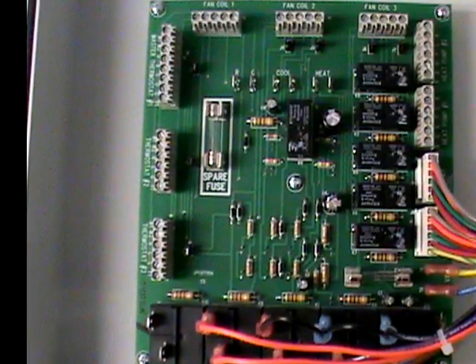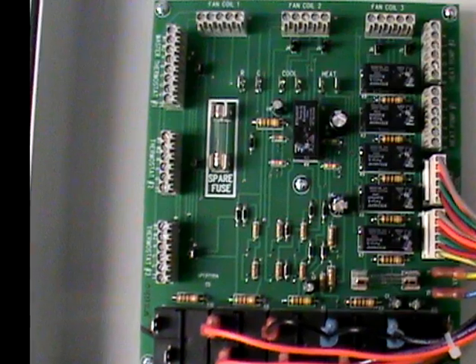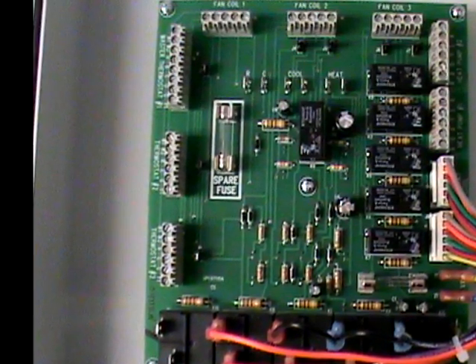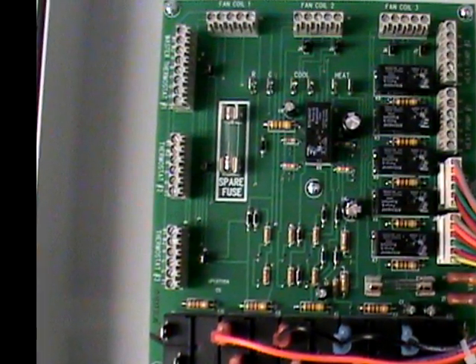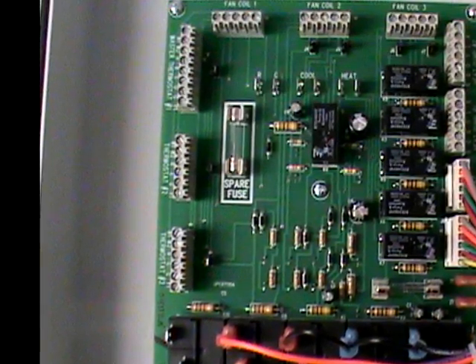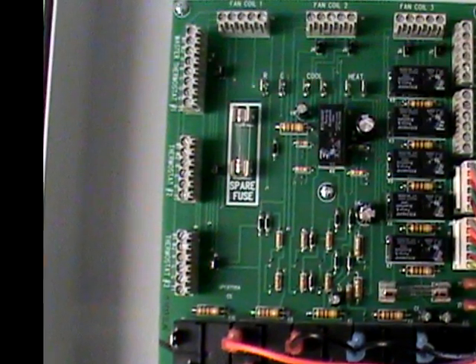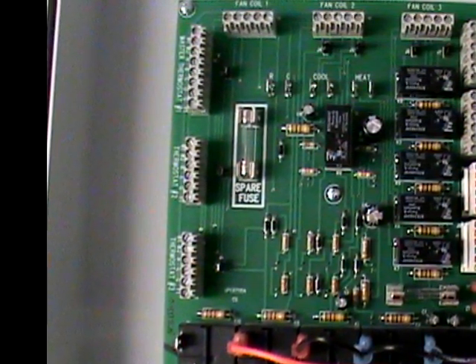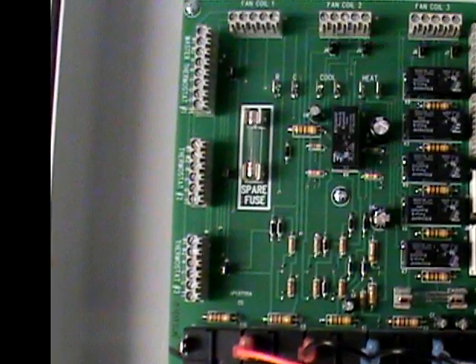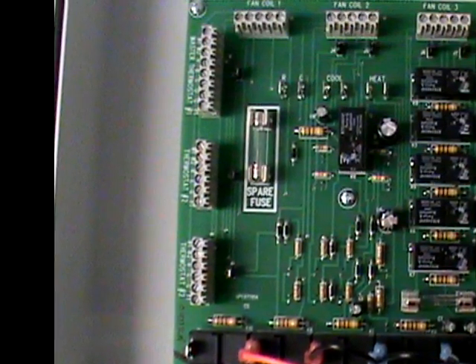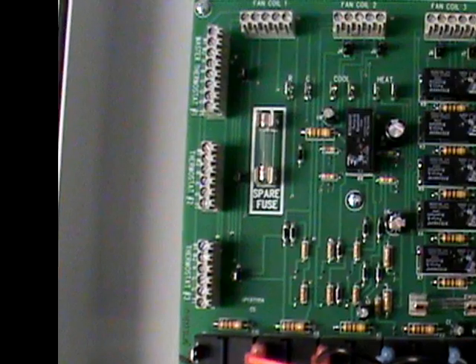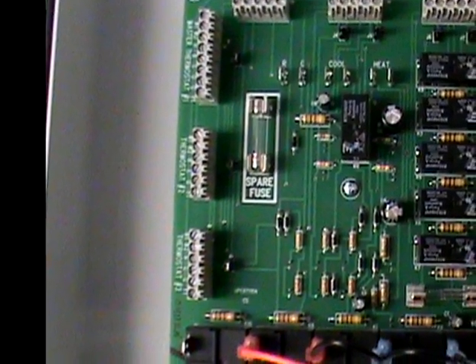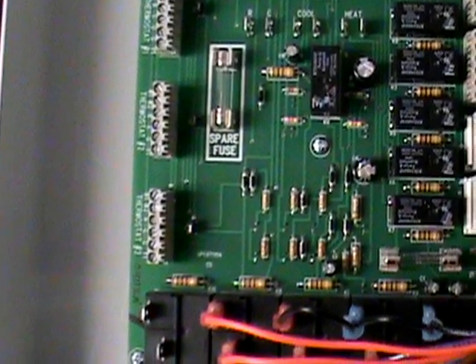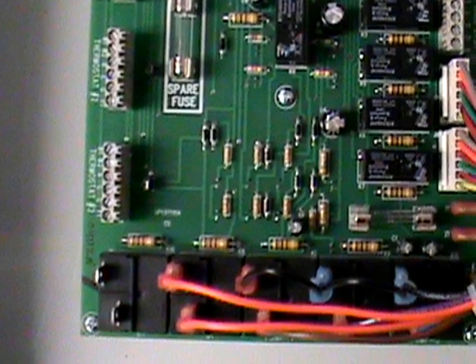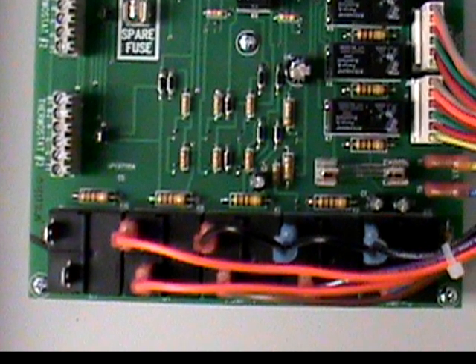Thermostat 1 is the master thermostat and determines whether the hydronic system is in heating, cooling, or off mode, as well as controlling fan coil number 1. Each thermostat block provides the following terminals for control: W1, W2, R, C, G, and Y1. Across the bottom of the circuit board are the relays for each of the 3 zones associated with the fan coils and thermostats.